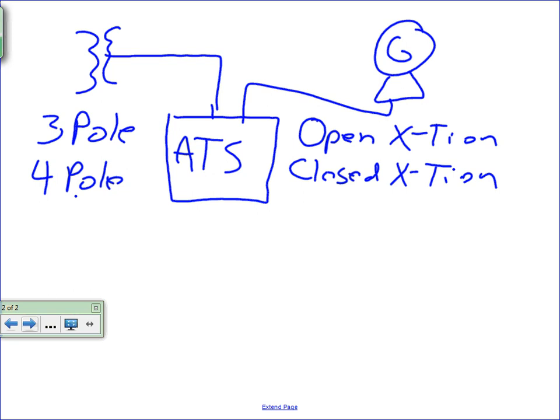you probably have to use the 4-pole transfer switch because they're probably going to bond this generator to ground. I mean, you always ground a generator, but they'll probably bond the neutral to ground, and that's the service entrance, right? So now they'll treat this like a service entrance. So it's deriving its own ground reference. And the utility is bonded. So now you have the potential of neutral currents flowing either direction, either to the generator or to the utility.